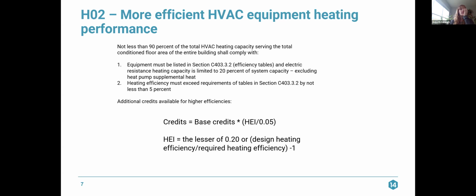And then the heating efficiency of the systems that you are taking credit for must exceed those tables by not less than 5%. So those tables in section C403. If you exceed those efficiencies by greater than 5%, you can gain additional credits. So you multiply the base credits that are listed in the C406 tables based on your occupancy. You multiply it by HEI divided by 0.05. HEI is the lesser of 0.20 or the design heating efficiency divided by the required heating efficiency minus 1. So we'll go through an example.